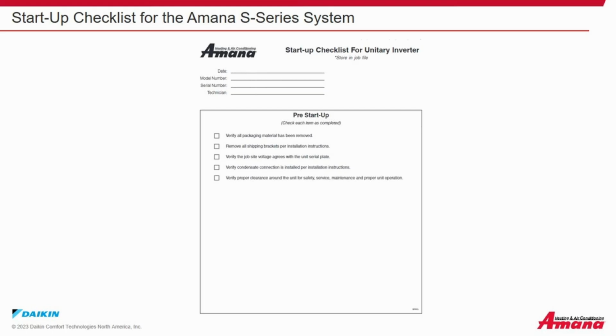Verify proper clearance around the unit for safety, service, maintenance, and proper unit operation. Verify proper waterproofing of all ductwork, roof curbs, and electrical connections. Check line set for leaks. Verify gas pressure to the unit is within the range specified on the serial plate. Check to ensure that all fan blades and wheels are secure.